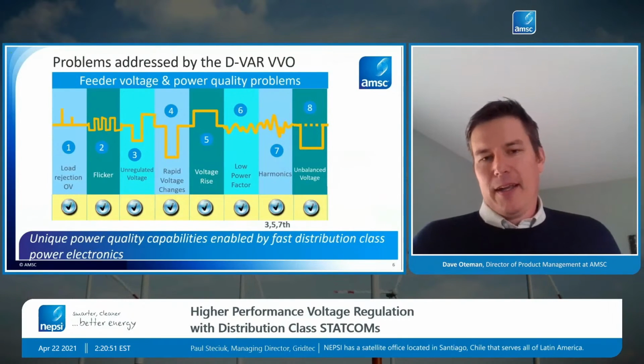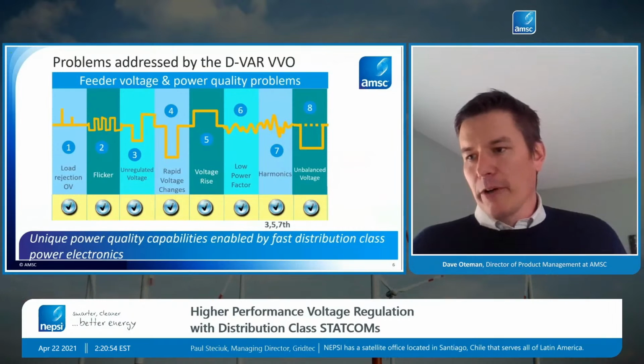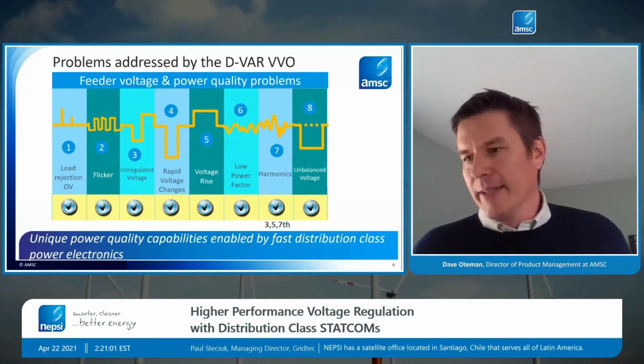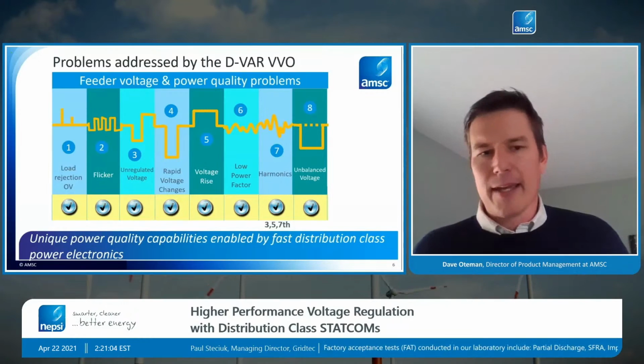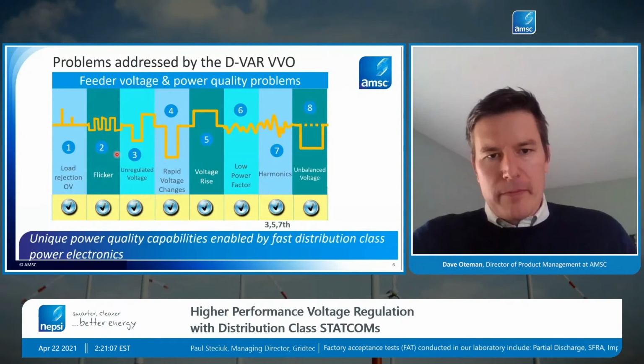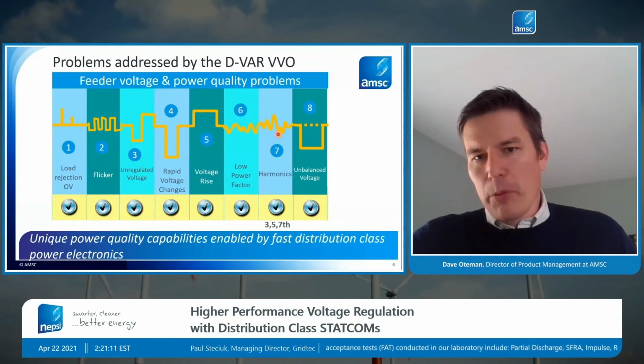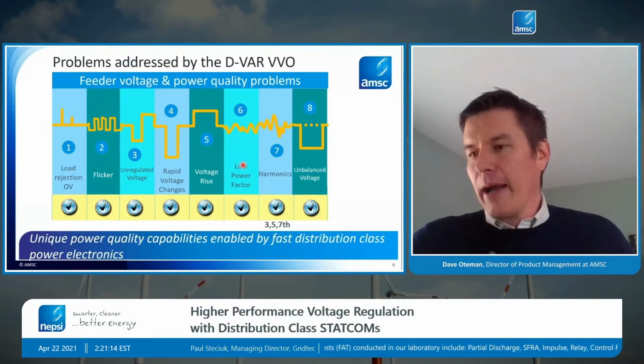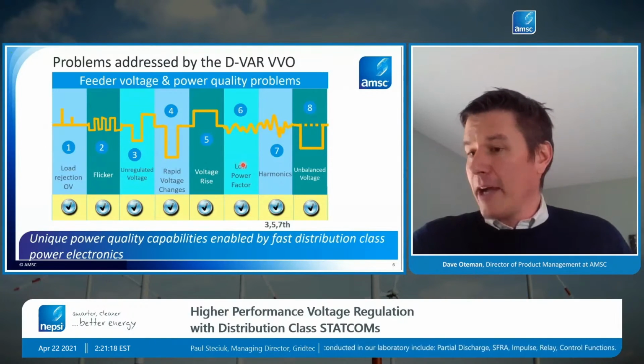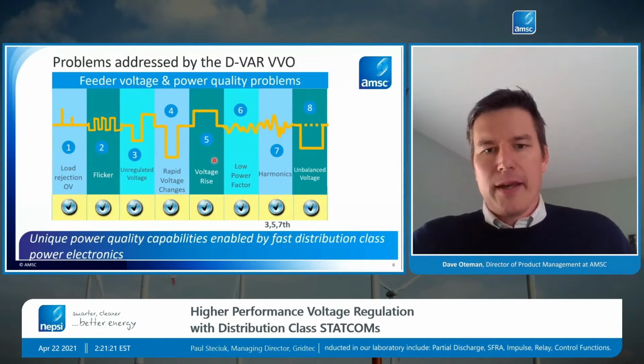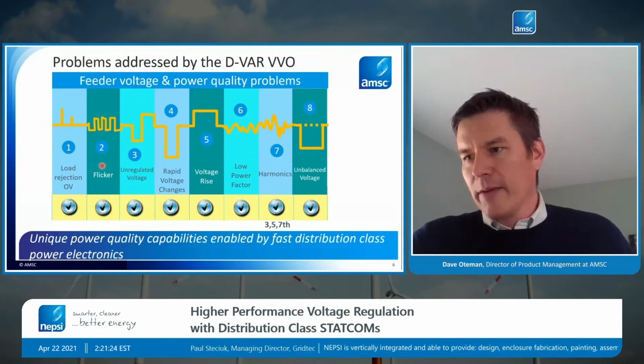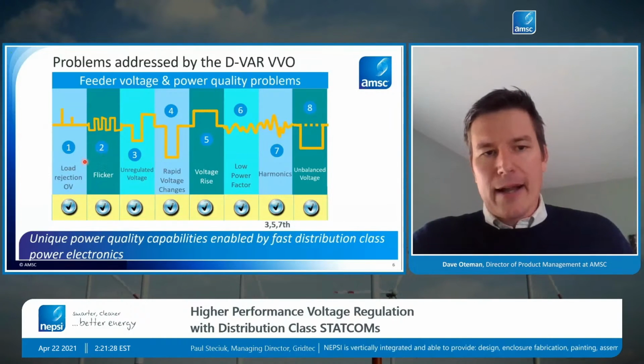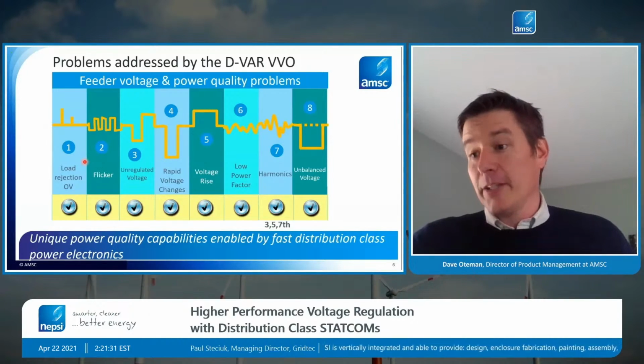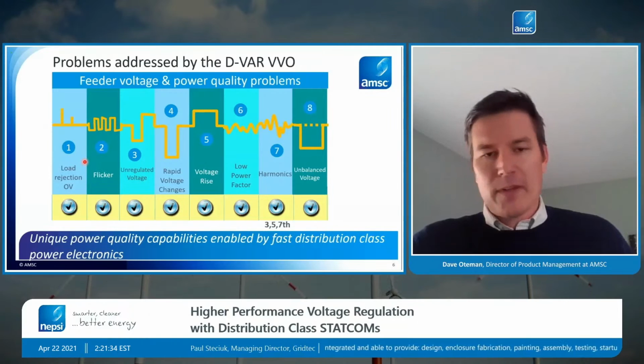Thanks for the question, Paul. We like to create a framework for power quality on the distribution system, and that's what I'm sharing in this slide. So we break it down into 8 different technical problems, you could say. We went over the regulated, unregulated voltage and low power factor. Those are pretty well addressed today by the power factor correction caps and the line regulators. That's the average voltage being managed. But as we can see, there are 6 other issues that are not well addressed today at all. And a STATCOM is ideally suited to address these other issues, in addition to the existing voltage and VAR management. So just briefly, let's swing through these.